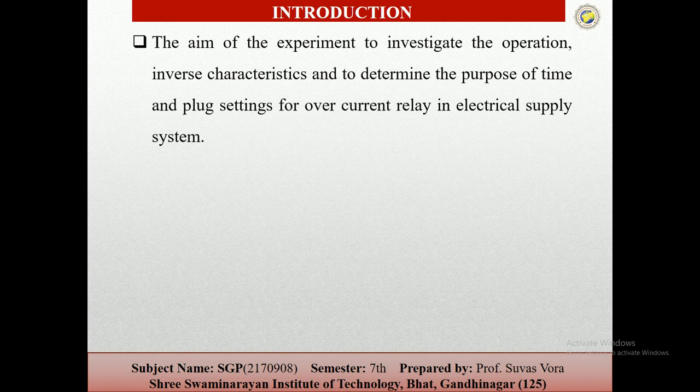Now start with the introduction. The aim of the experiment is to investigate the operation and inverse characteristics, and to determine the time and plug setting for the overcurrent relay in an electrical supply system. It means the minimum pickup value of the deflecting force of the electrical relay is constant, so the deflection force of the coil is proportional to the number of turns and the current flowing through the coils.